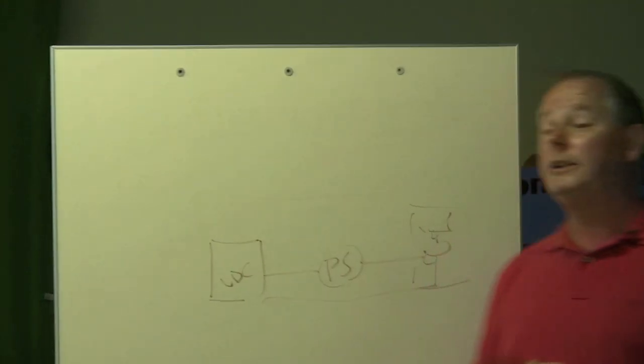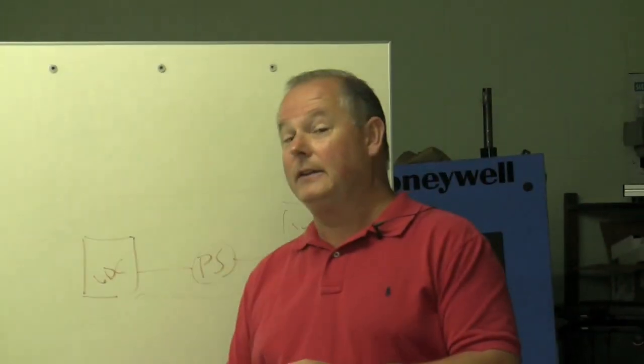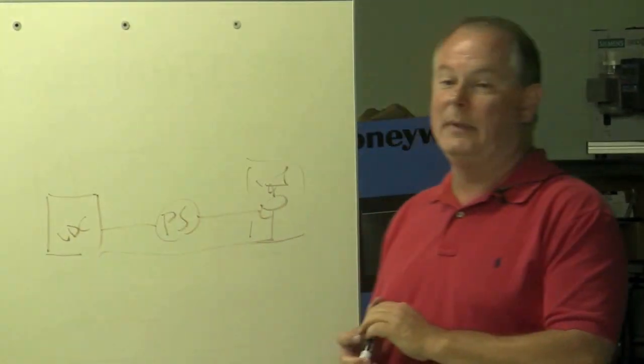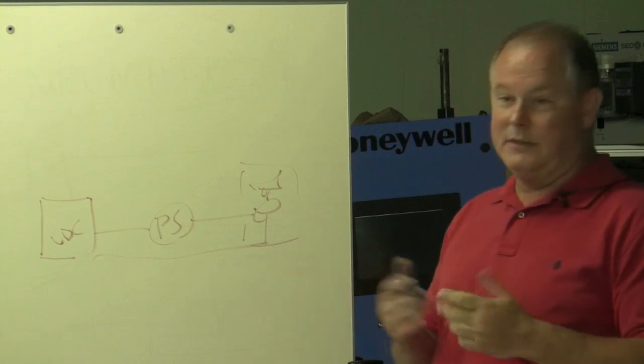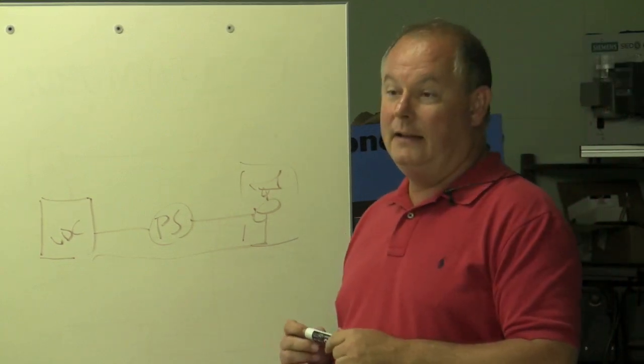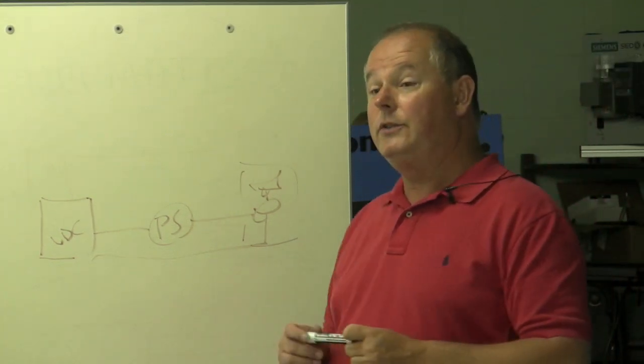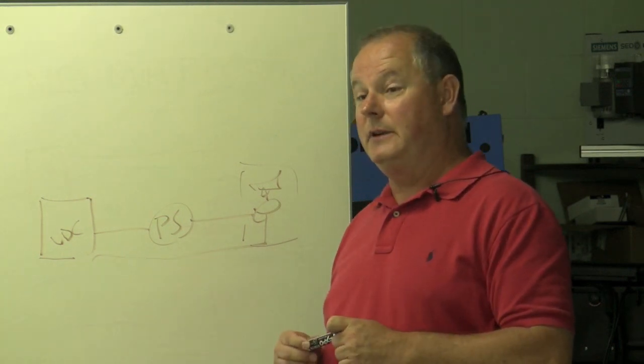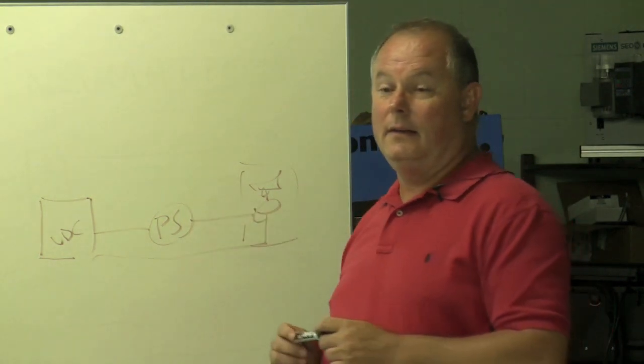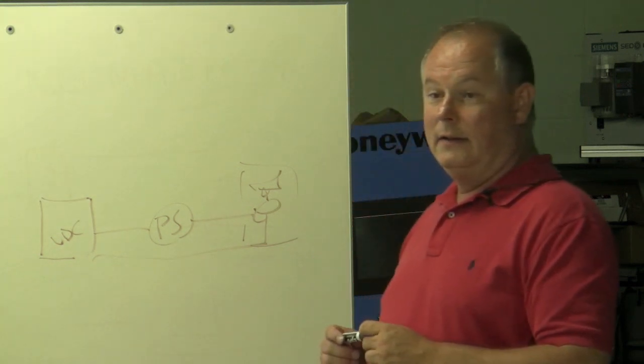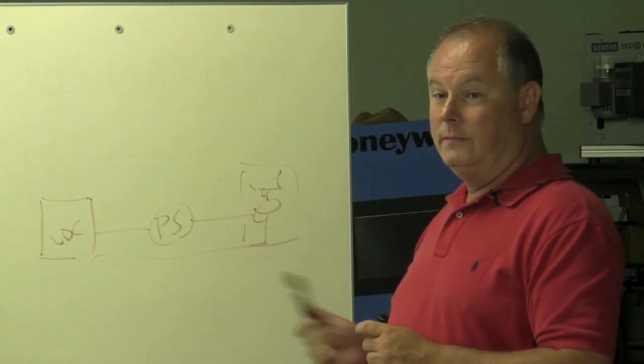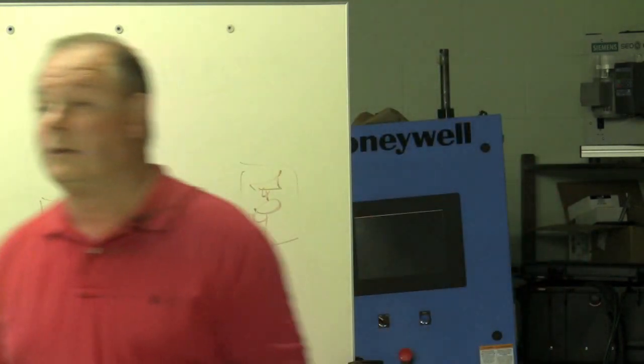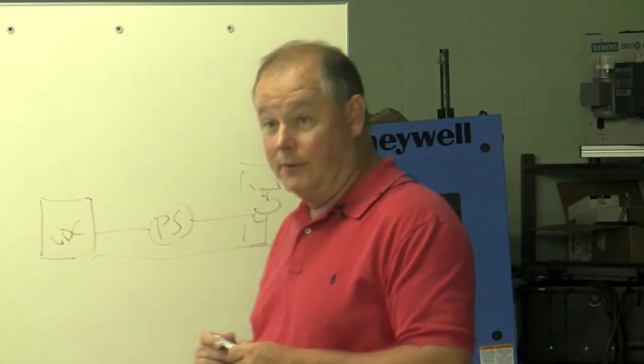Any questions about that? I'd say older rather than higher end. Foxboro made a ton of four-wire transmitters. It was just a decision they made, and others have done it, but you could do a pressure transmitter that's powered with 120 volts and drives 4 to 20 over to the controller. So one is powered in the loop, and one is powered externally in the loop. That's correct.